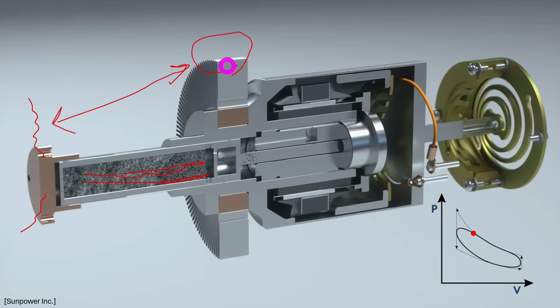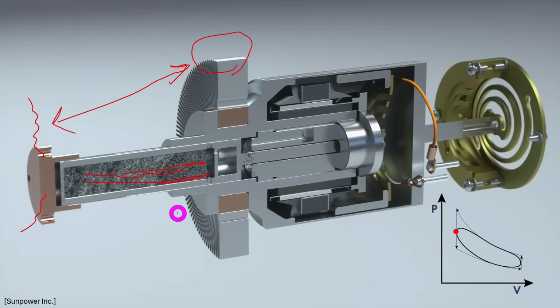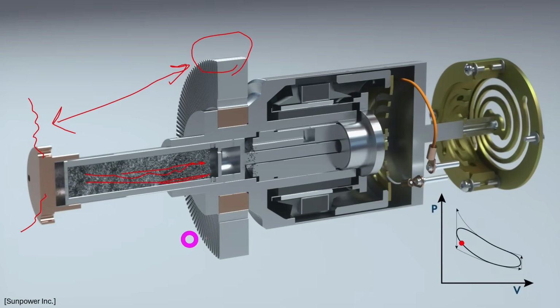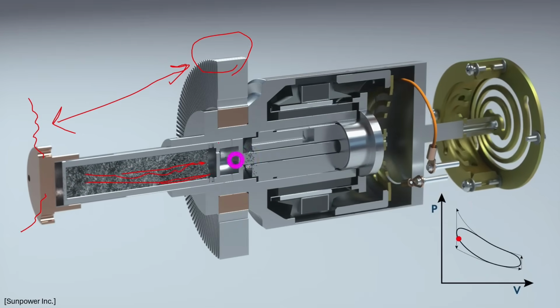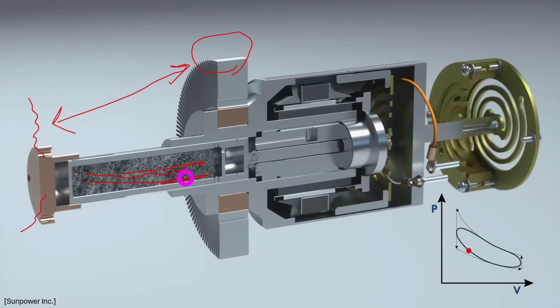If I end up heating up this area, this cold tip will simply not be able to reach its lowest possible temperature, and the entire efficiency of the system will be heavily affected. So we have to be very careful on how we manage the thermal profile of this, and I'll show you what we can do about that.